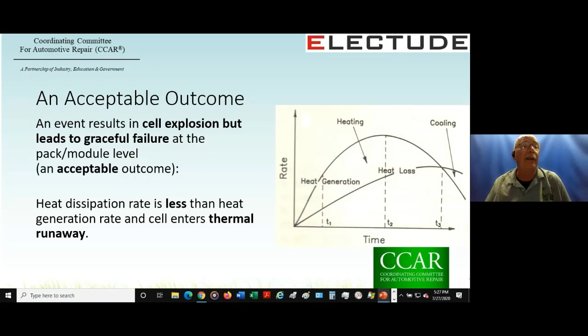And in this instance, for an acceptable, we're going to say that failure occurs within the cell that leads to an increase in temperature. Let's go with overcharge. Reaction within the cell creates additional heat and gas. The reaction zone expands. Heat dissipation rate is less than the heat generation rate, and the cell enters thermal runaway. Additional heat and gas are produced. The cell vents, possibly explodes, but nearby cells heat up, but not driven to the point of thermal runaway. The expansion of the failure is stopped at the initial cell. Probably going to look something like this. And once again, my poor attempt at thermal scan, or you can think of it as clown makeup.